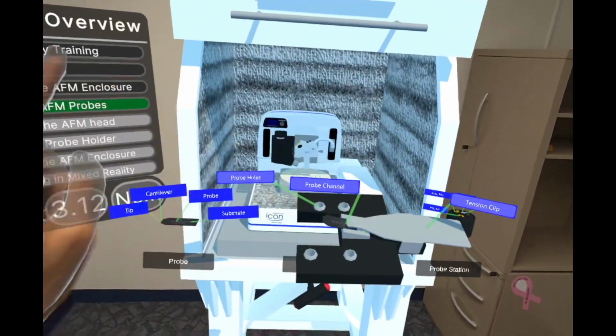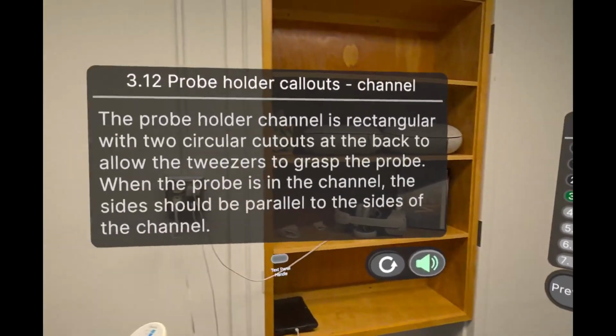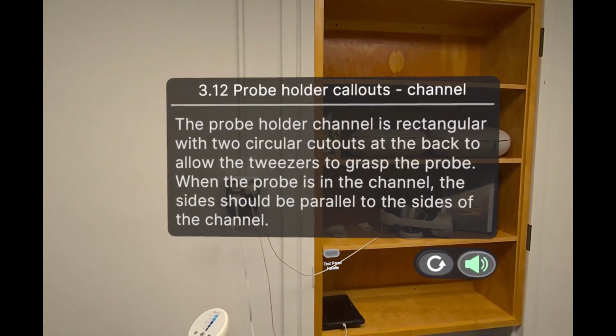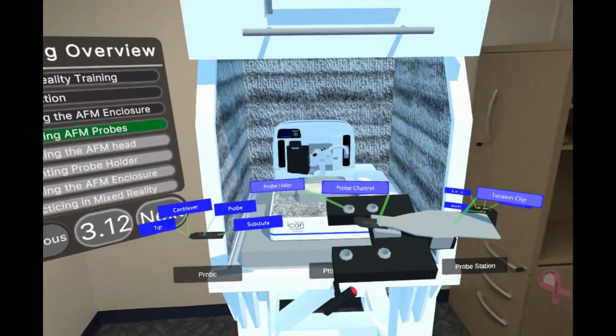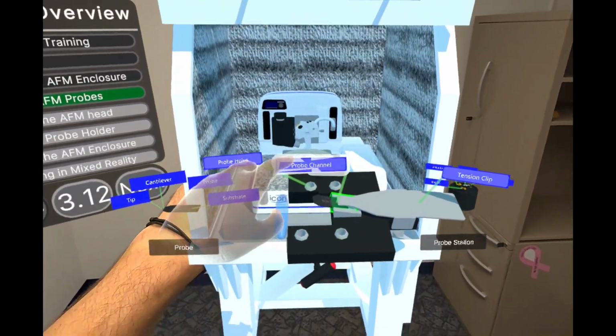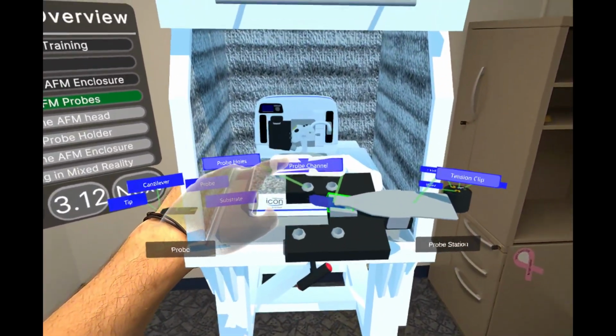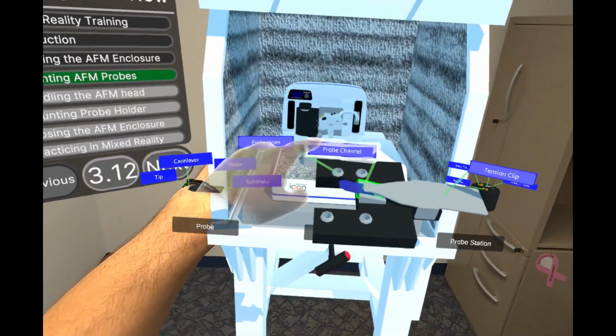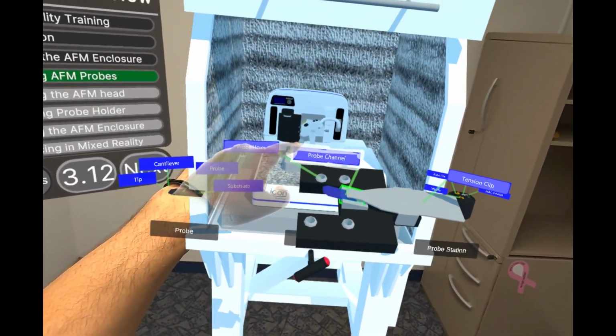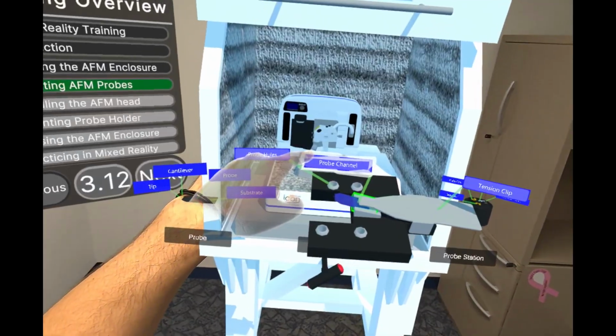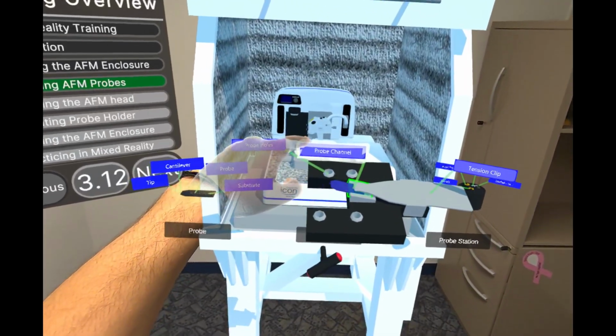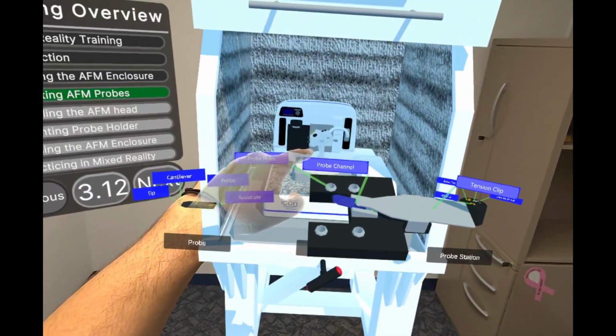The rectangular recess on the probe holder is the probe channel where the probe sits. The channel has a 15-degree angle to it. This helps the probe slide into position at the bottom of the channel when you tap the probe station gently on the table. There are 2 circular cutouts at the back of the channel to allow the tweezers to come in and grasp the probe when removing it.